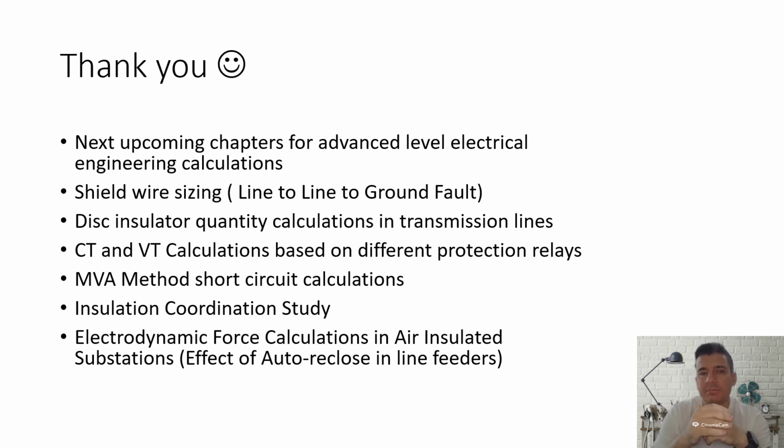The next step: maybe most of you are very aware of this MVA method. By the way, I am also using this one so frequently. It's a very effective and very accurate way to calculate short circuits. You don't need any kind of software for this one, but you can verify even with any software. I will not mention any software here, but you know most of them. Then you will see how accurately and how easily you can calculate any short circuit level, including not only the three-phase, but also the line to ground and line to line fault calculations.